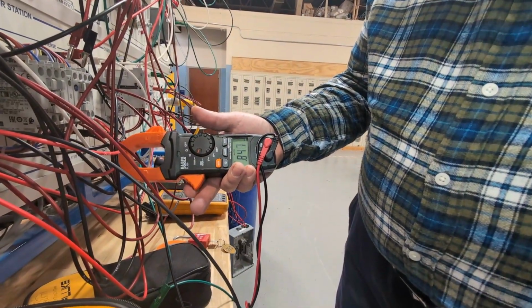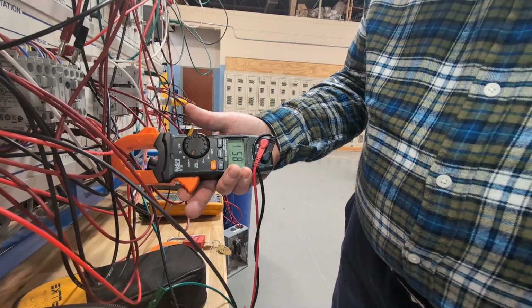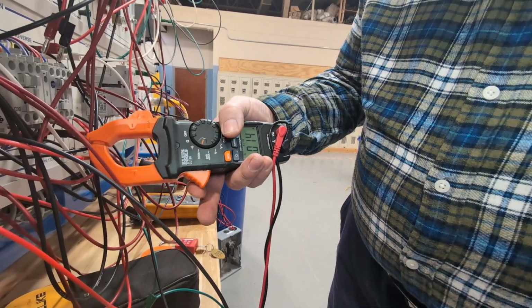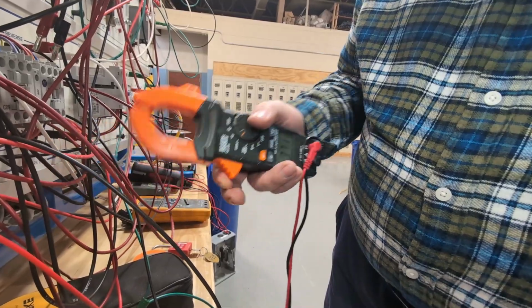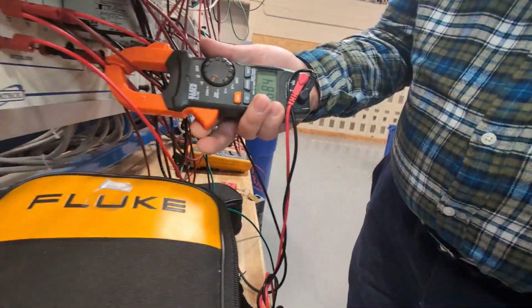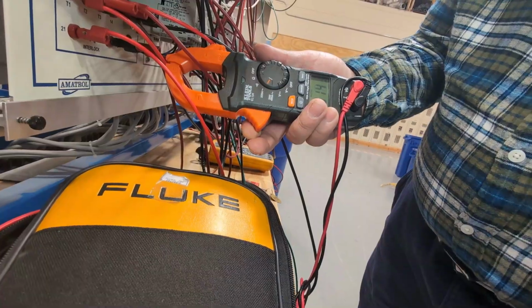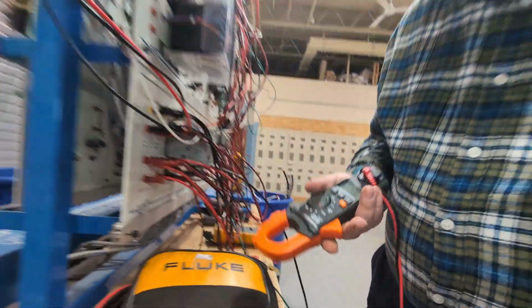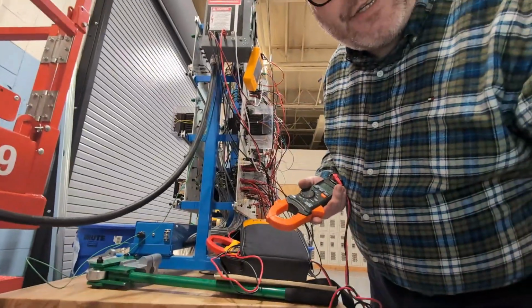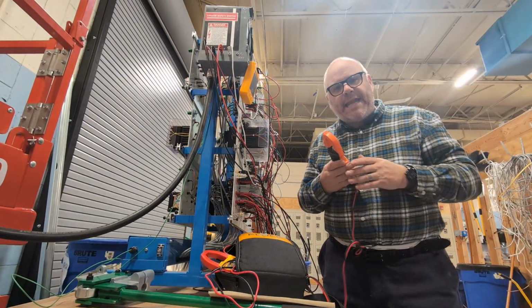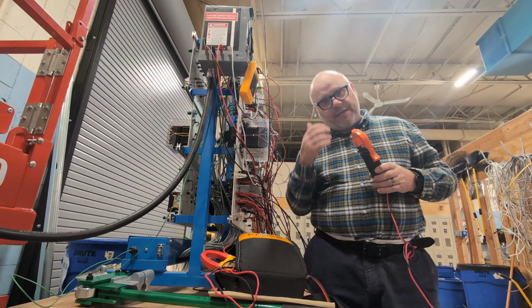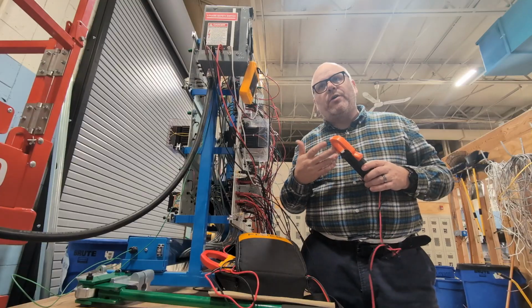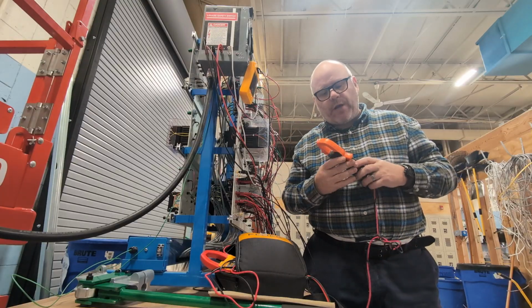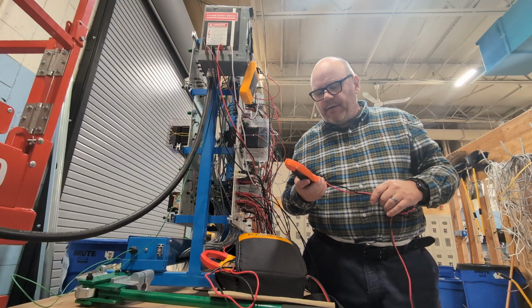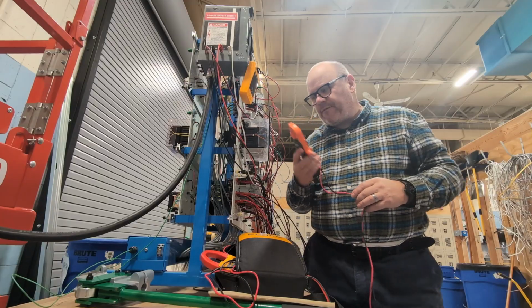That's my flow of electricity, 0.85 amps. Check each phase - 0.865 amps. Check the other phase. That is checking amperage. I would recommend that if you keep having something overload or trip, and it's not a short, check continuity. But if you have that overload issue, do your amperage check and verify.